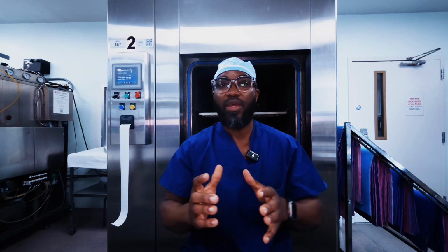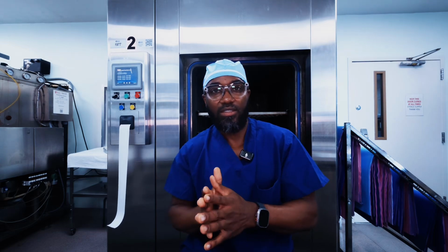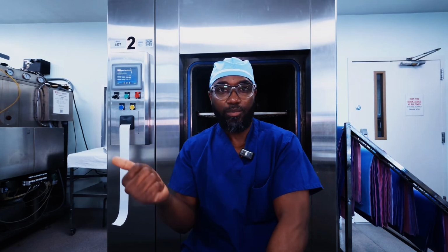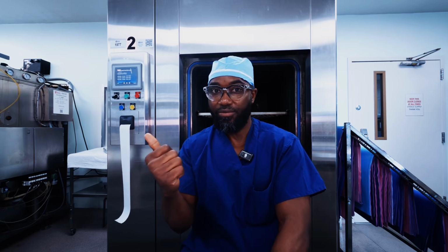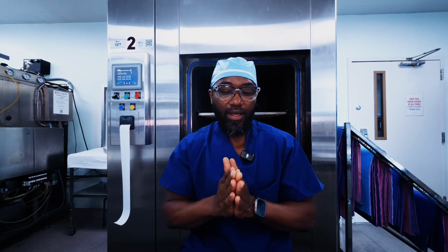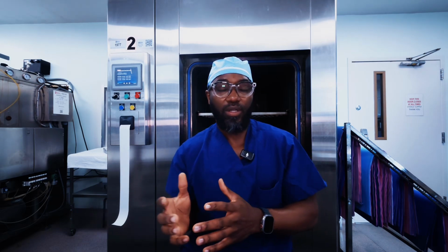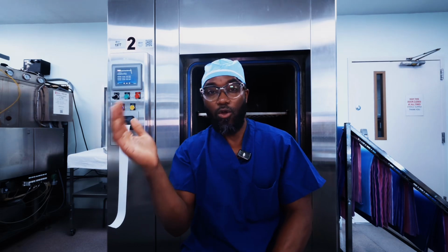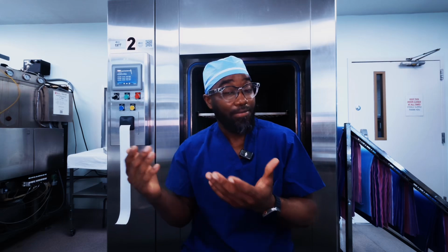Before these instruments make it to the operating room, they undergo a series of processes from cleaning, inspection, lubrication if required, assembly, and then sterilization. And before they go into sterilization, whether it's high temperature or low temperature sterilization, there is equipment used to sterilize them. Before we use this equipment, we have to test it for efficacy to make sure that what we're using for sterilization actually works in the process.